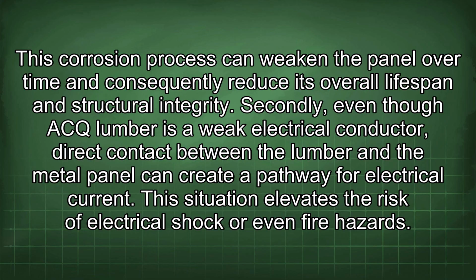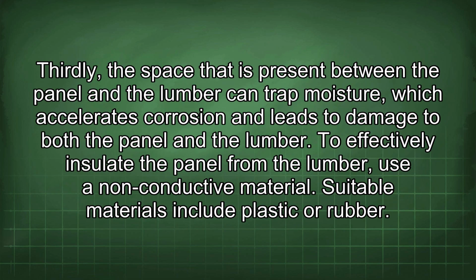Secondly, even though ACQ lumber is a weak electrical conductor, direct contact between the lumber and the metal panel can create a pathway for electrical current. This situation elevates the risk of electrical shock or even fire hazards. Thirdly, the space that is present between the panel and the lumber can trap moisture, which accelerates corrosion and leads to damage to both the panel and the lumber.